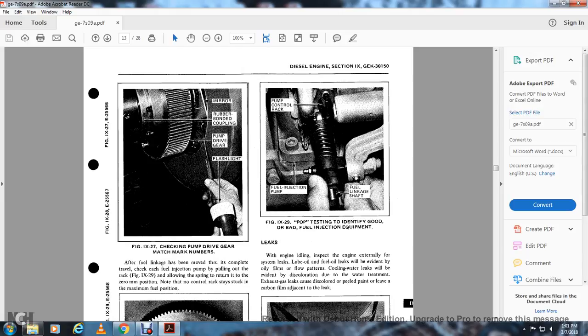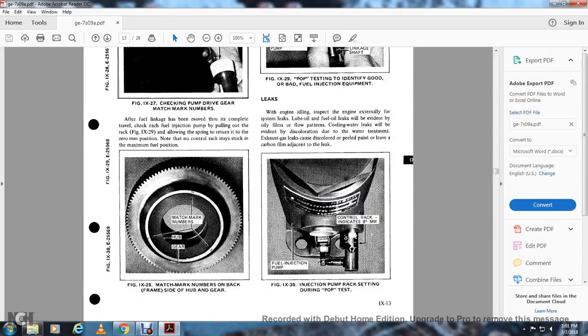Leaks: With the engine at idle, inspect the engine externally for system leaks. Lube oil and fuel oil leaks will show only as films and flow patterns. Cooling water leaks can be identified by discoloration due to water treatment. Exhaust gas leaks cause discolored, pale paint and leave carbon deposits adjacent to the leak.